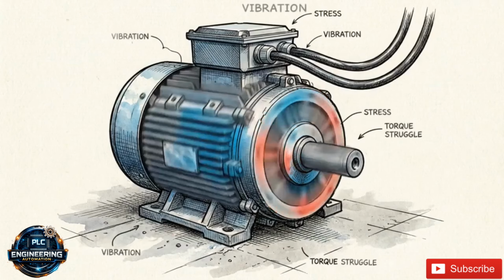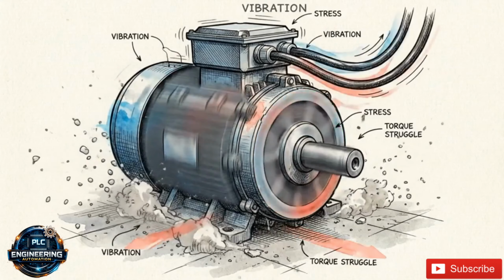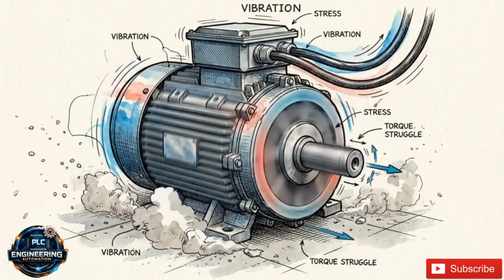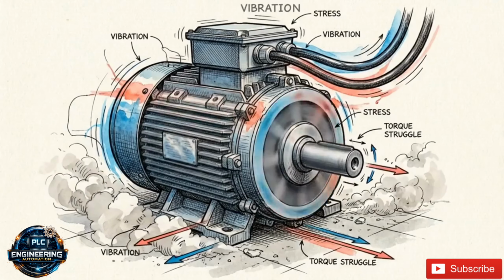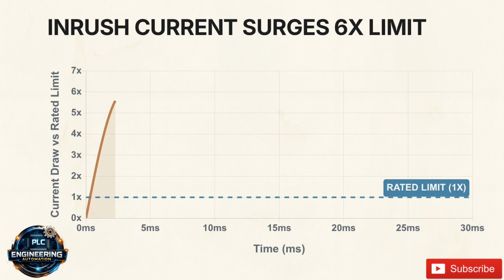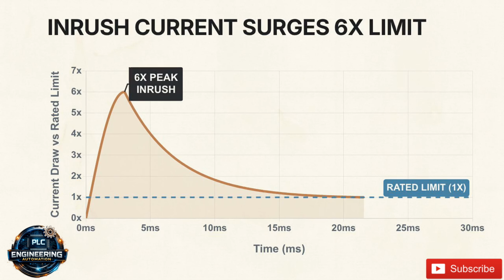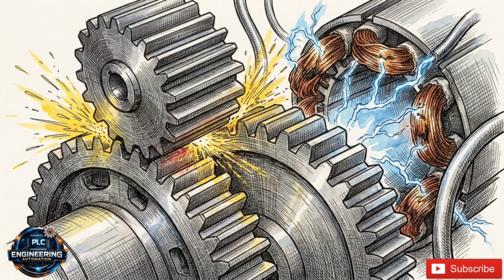If you connect a three-phase industrial motor directly to the AC grid, you surrender all control to the raw physics of the power supply. The motor draws massive inrush currents, up to 6 times its rated limit to break inertia. Mechanical linkages suffer extreme torque shocks, and the internal windings remain entirely vulnerable to unpredictable grid voltage spikes.